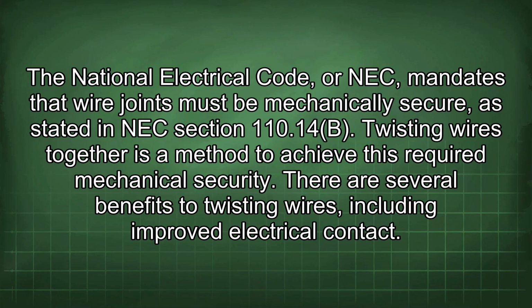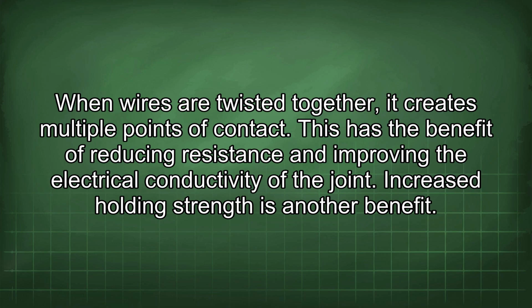The National Electrical Code, or NEC, mandates that wire joints must be mechanically secure, as stated in NEC Section 110.14(B). Twisting wires together is a method to achieve this required mechanical security. There are several benefits to twisting wires, including improved electrical contact. When wires are twisted together, it creates multiple points of contact. This has the benefit of reducing resistance and improving the electrical conductivity of the joint.